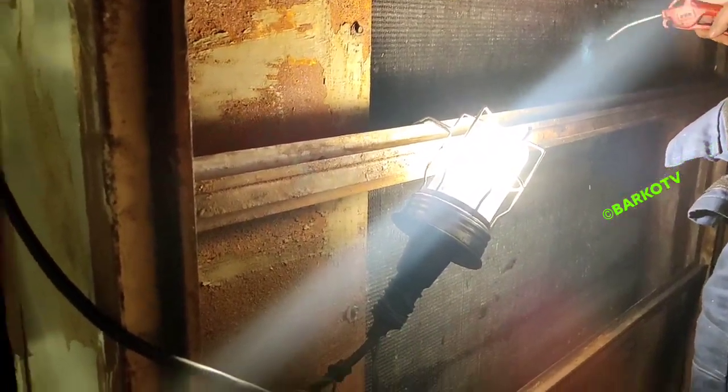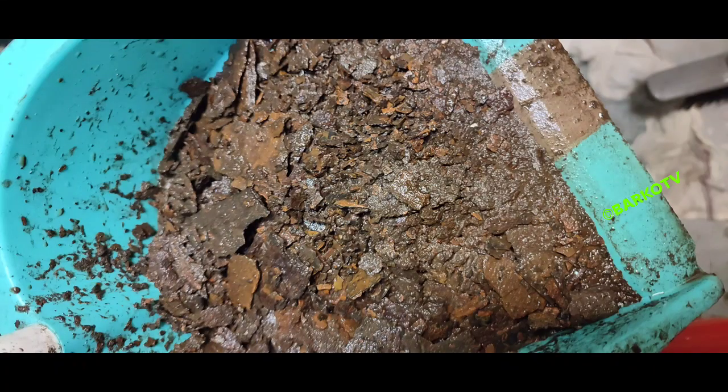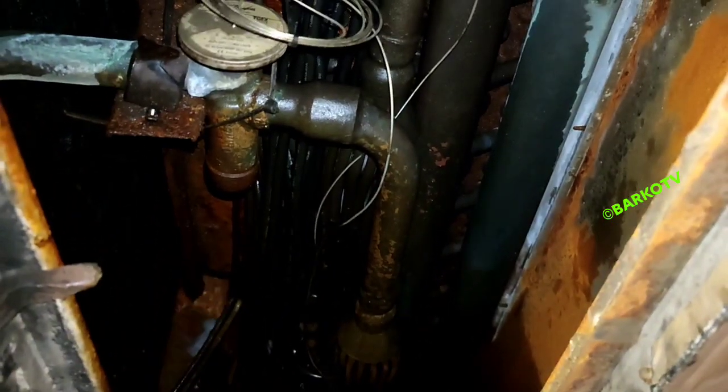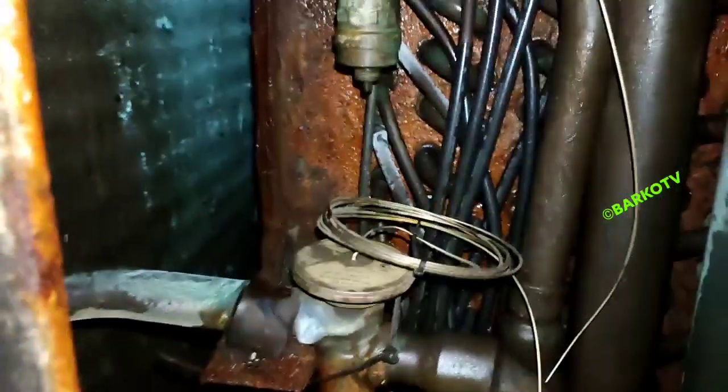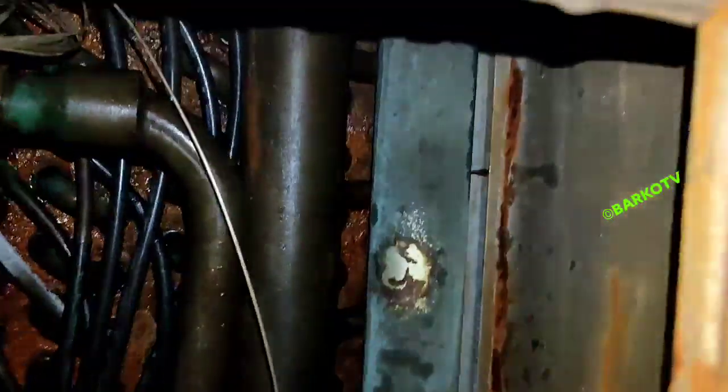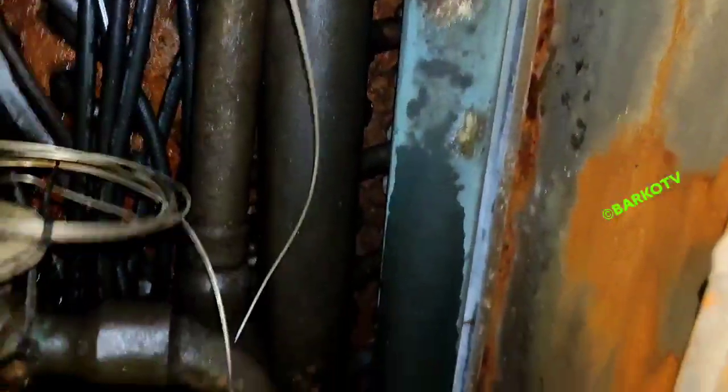We will schedule to clean using a high-pressure washer. This is rust here, and the evaporator is too brittle. You need to request a dry dock to replace this one — maybe two more years, I don't know. But right now it is running smoothly.